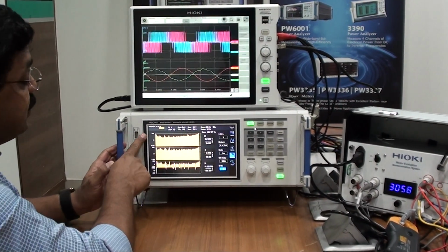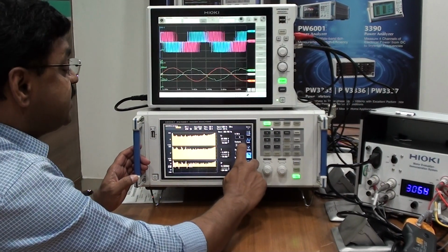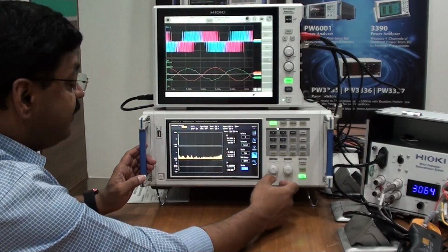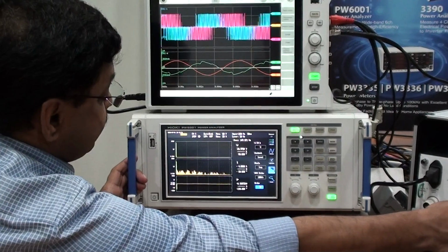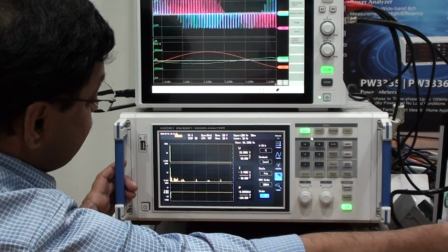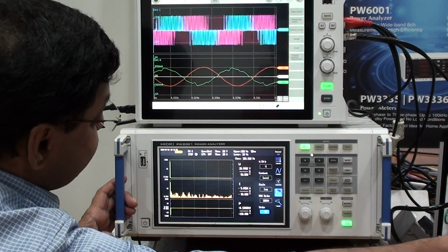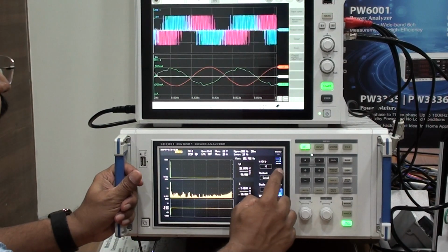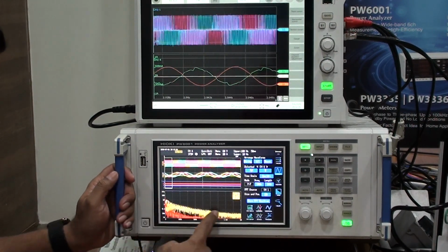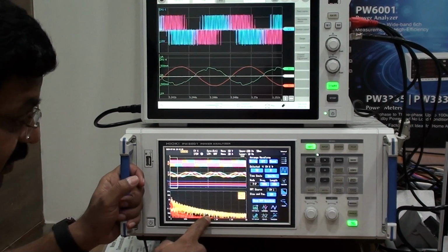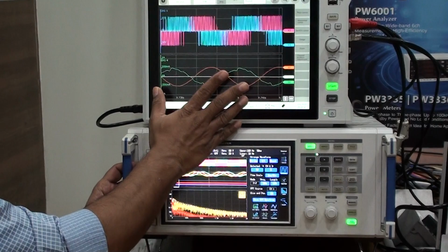This is the motor harmonics, the voltage harmonics, the current harmonics, and the power harmonics. So this is the percentage of fundamental, and we have a level of harmonics to give you the current harmonics. As you see, the harmonics differ according to how you look at it. We also have FFT on it. So this is your voltage FFT and the current FFT. What you could do is a proper study of this FFT using the recorder.